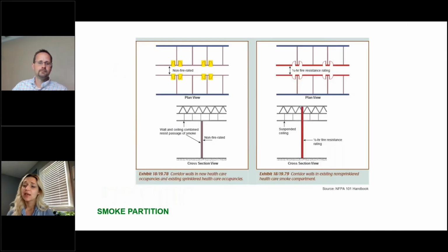We'll see this most commonly in healthcare, and here are perfect examples for the corridors. On the left side, you'll see corridor walls in new healthcare or existing healthcare that are sprinklered. If we have a sprinklered building, we are permitted to just provide these smoke partitions or smoke resistive construction in the corridor, non-rated. And on the right side, you'll see corridor walls in existing non-sprinklered healthcare. Non-sprinklered healthcare gives me jitters a little bit, but there are still some out there that are non-sprinklered. And when we run into that, we're required to have half-hour fire resistance rated corridors.